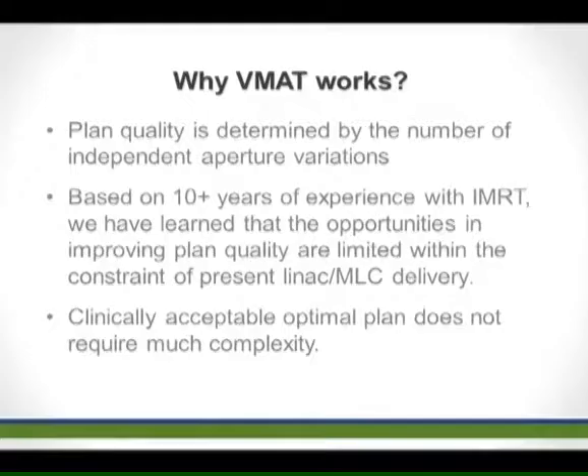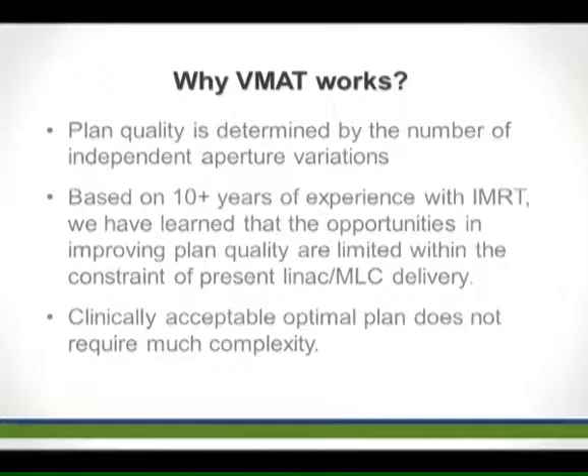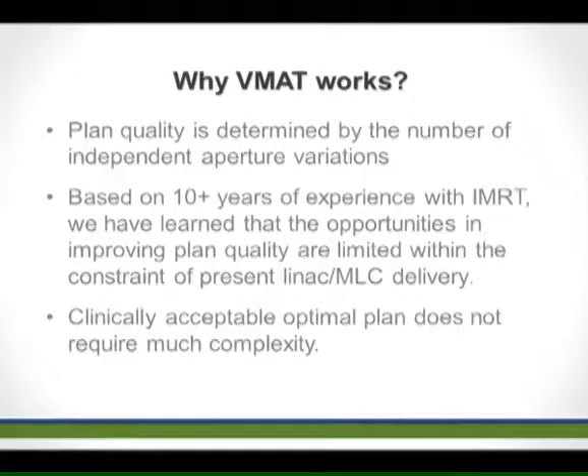Why does VMAT work? Plan quality is determined by the number of shape changes, and clinical equipment has its limitations. The gantry can only move with a certain speed variation, the dose rate can only change at a certain rate, and MLC leaves can only travel at a certain speed limit. Most clinical cases are not so complex that they require a very large number of degrees of freedom. Therefore, VMAT can be efficient for many clinical cases.